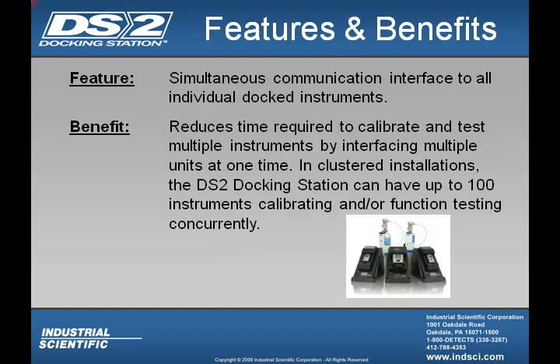Also on your docking station, you have simultaneous communication interface to all individual docked instruments. What this will do is reduce the time required to calibrate and test multiple instruments by interfacing multiple units at one time. In a clustered installation, the DS2 can have up to 100 instruments communicating and/or function testing concurrently.